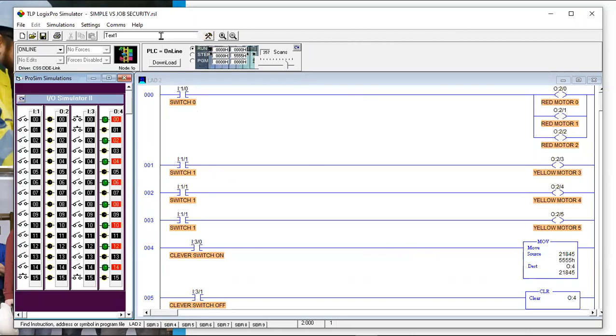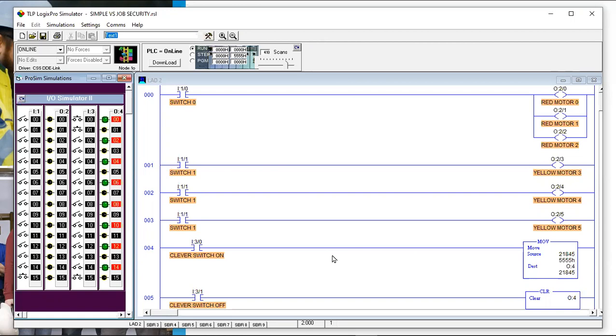You could search for 'motor four', you could search for the output address — output four-six or four-four — and it never appears anywhere in this entire program. It doesn't appear there. So this is hard to deal with. There's no denying this logic is effective, efficient, and pretty slick — one rung to turn it all on.